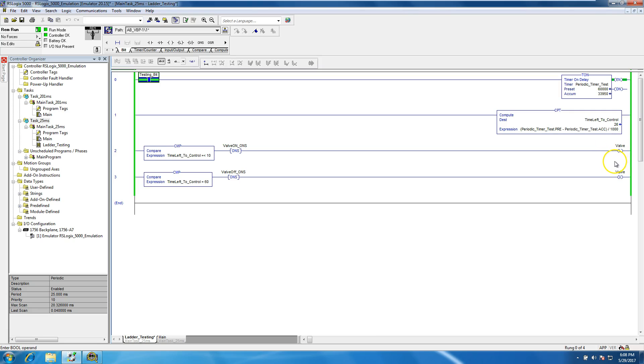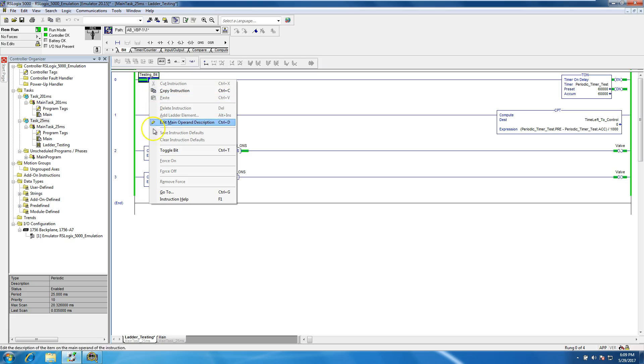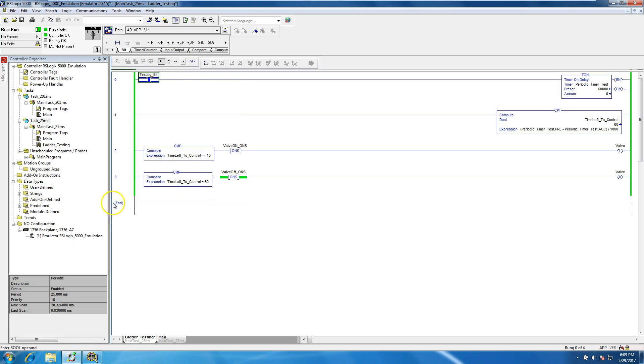This will be a latch and an unlatch. As soon as it gets below 10 seconds the latch fires. I'll take the test bit off and show the unlatch. Right now it's latched in using only a one-shot — so it only held for one scan cycle. If I untoggle the test bit the timer resets, and when the compute recalculates the time left equal to 60, it will unlatch.